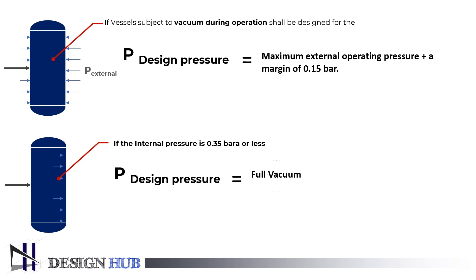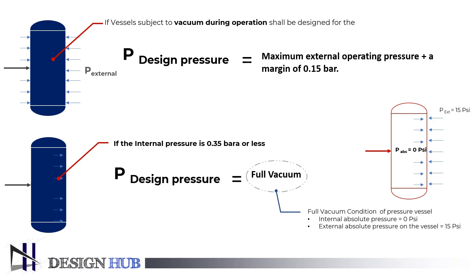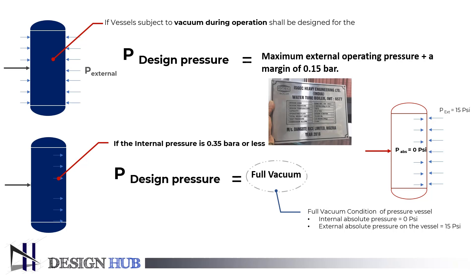Now the question arises, what is full vacuum condition? Full vacuum condition of the pressure vessel is defined in ASME: internal absolute pressure equals 0 psi, external absolute pressure on the vessel equals 15 psi. This is the nameplate for the pressure vessel designed at full vacuum condition.